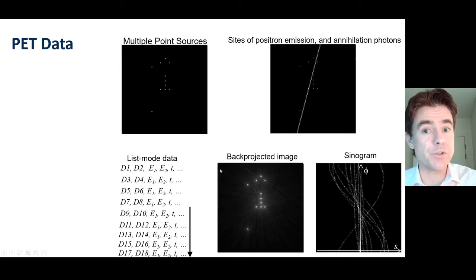A linear system means if we have multiple point sources in the PET scanner field of view, we get linear superposition of all the separate sine wave responses. The back-projected image is the superposition of all those back-projected intersection points, but we're limited by noise here. The list-mode data just keeps going on.